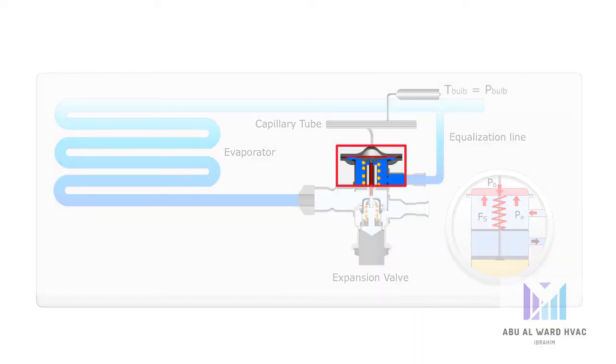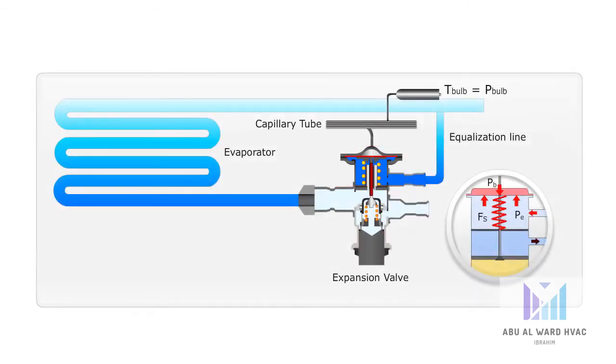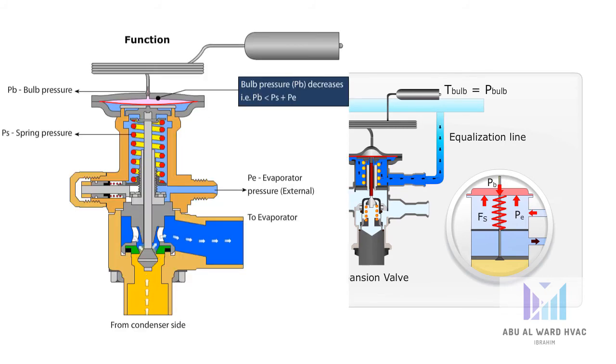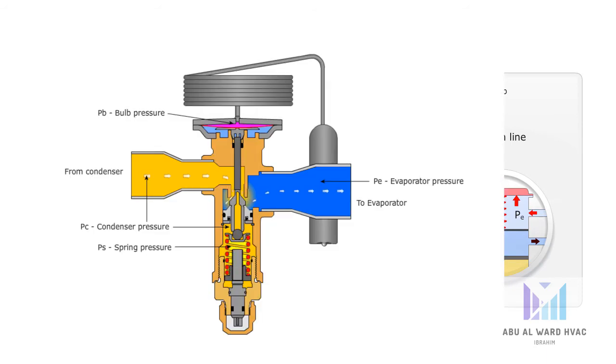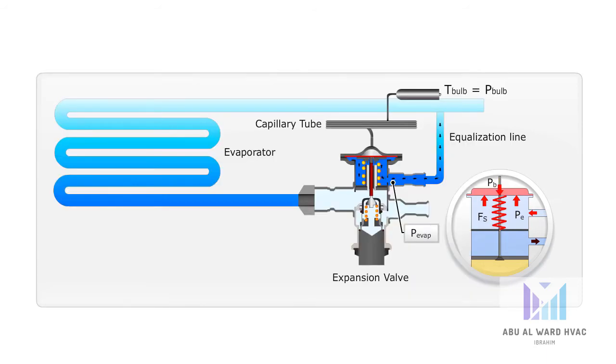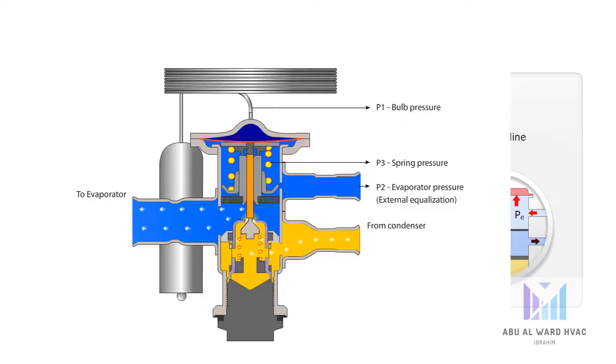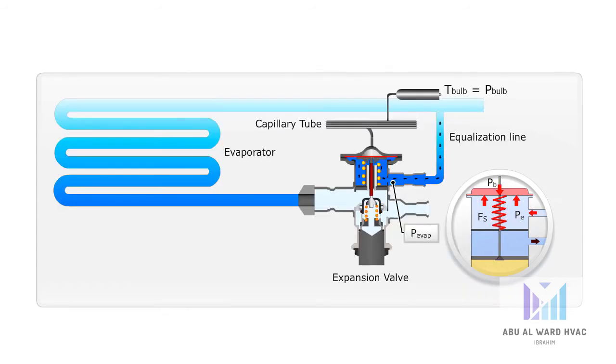The TXV senses the bulb temperature at the evaporator outlet. The bulb temperature is, by means of evaporating charge, converted into pressure P-bulb, which through the capillary tube is transferred to the top side of the diaphragm. The evaporating pressure Pe valve is led to the underside of the diaphragm, either through the external equalizing connector or through a hole inside the valve.